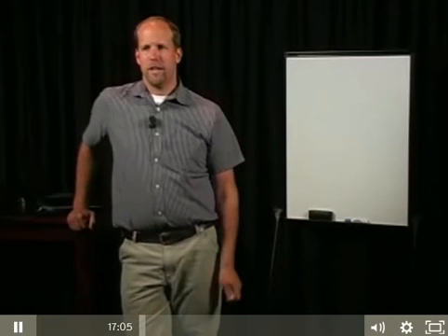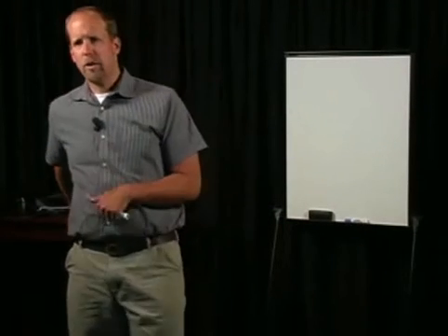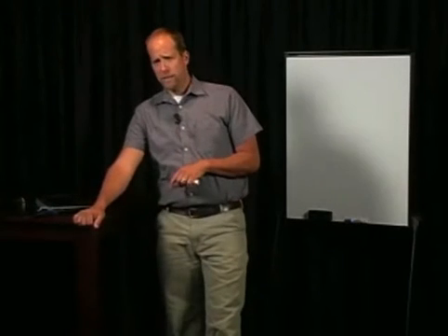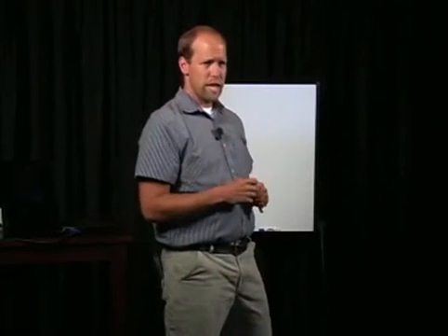It is possible to reach 100% relative humidity without changing the amount of water vapor in the air, its vapor pressure or absolute humidity. All that is required is for the temperature to drop to the dew point. Relative humidity and temperature often vary within a room, while the absolute humidity in the room air can usually be assumed to be uniform. Therefore, if one side of the room is warm and the other side of the room is cool, the cool side has the higher RH than the warm side. The highest RH in a room is always next to the coldest surface. This is referred to as the first condensing surface, as it will be the location where the condensation occurs first if the relative humidity at the surfaces reaches 100%.